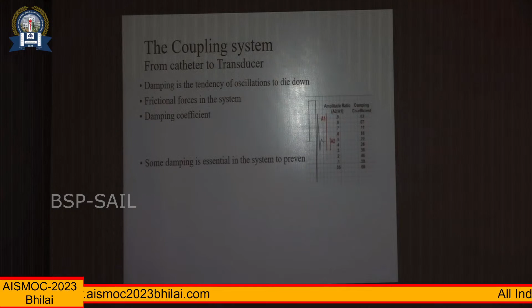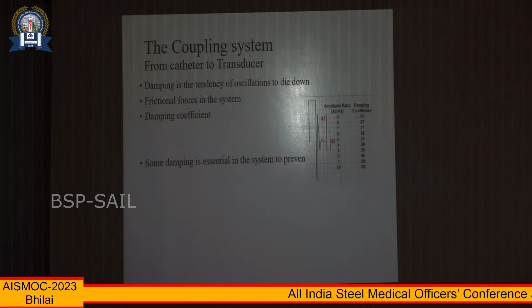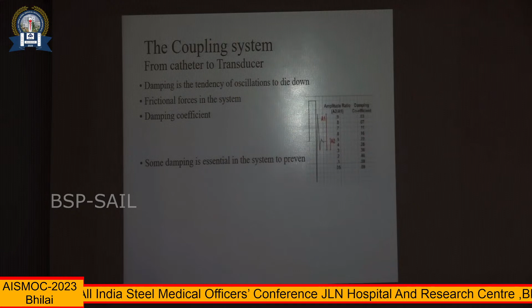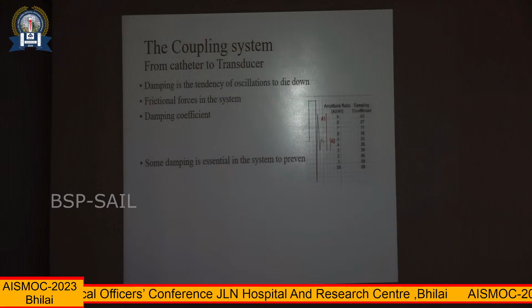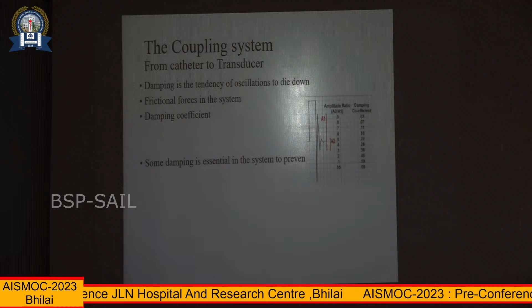Okay. Now the other aspect. So first was understanding the frequency of the transducer. Second is to understand how the principle of the Wheatstone bridge works. And third is how to understand whether the system is optimally damped or under-damped. For example, if you drop a ball, the ball will maybe bounce a few times before it dies down, right? So it depends on how hard the surface is, how much pressurized the ball is. All these factors will cause the ball to bounce.